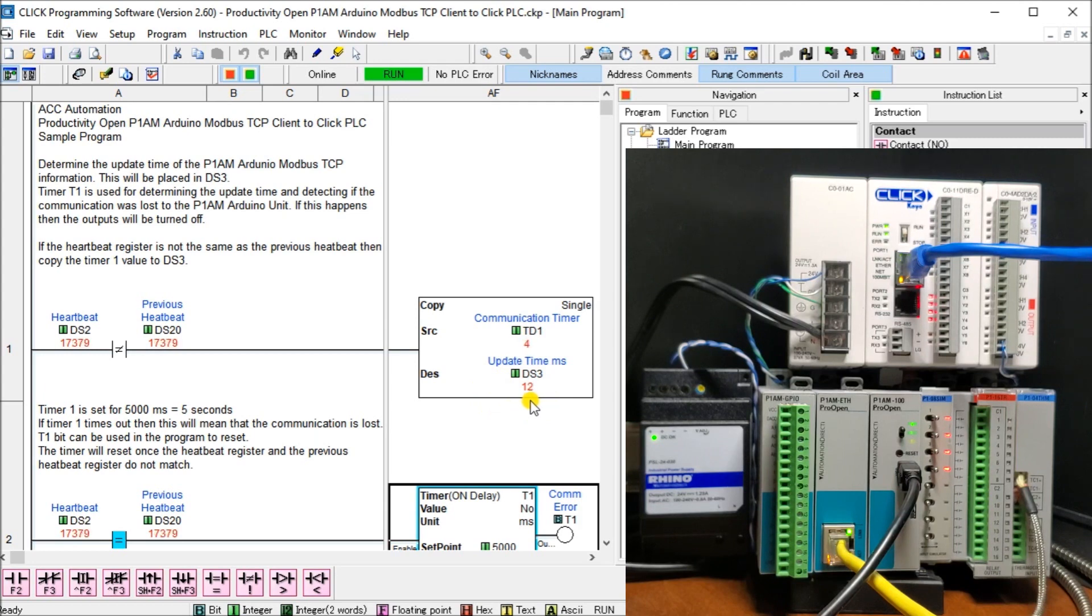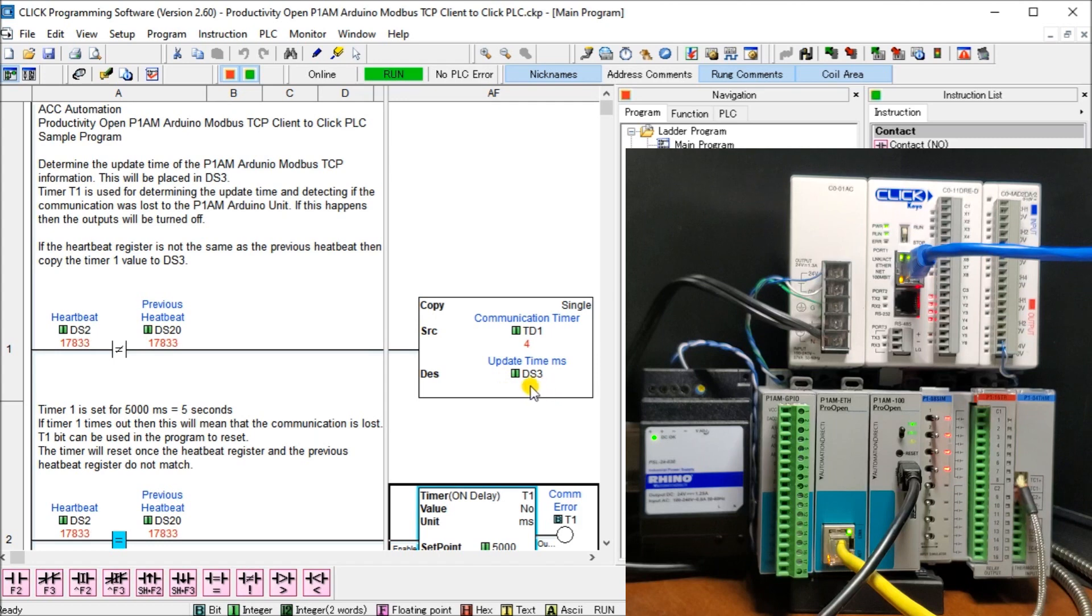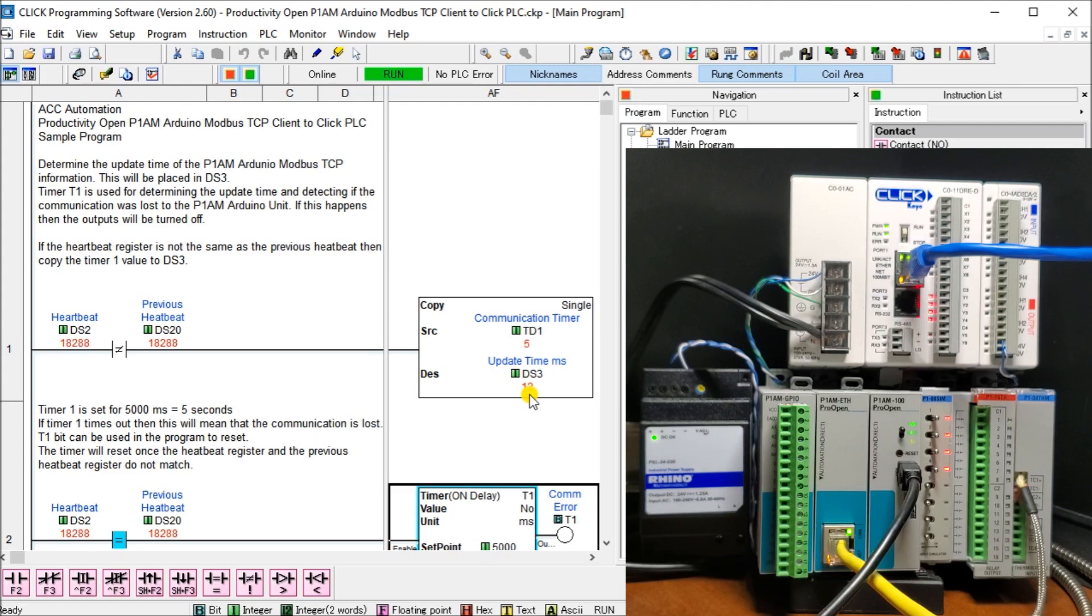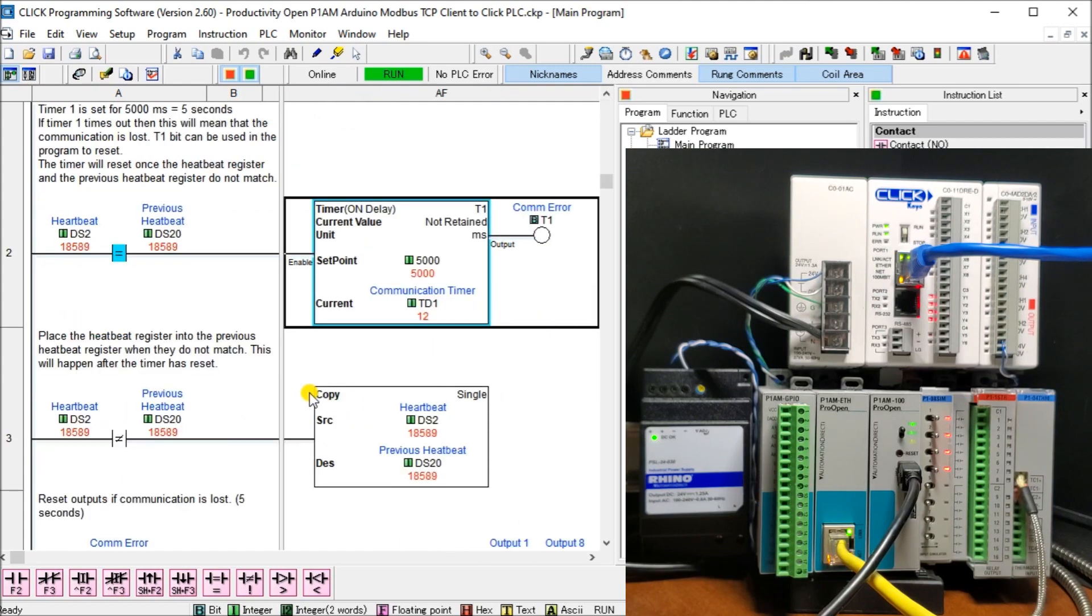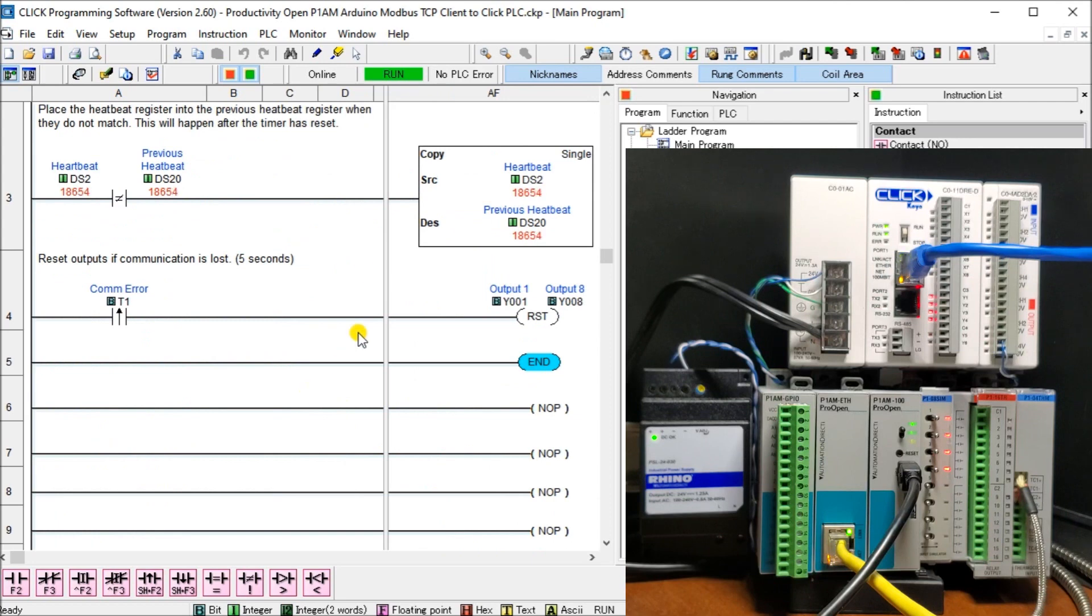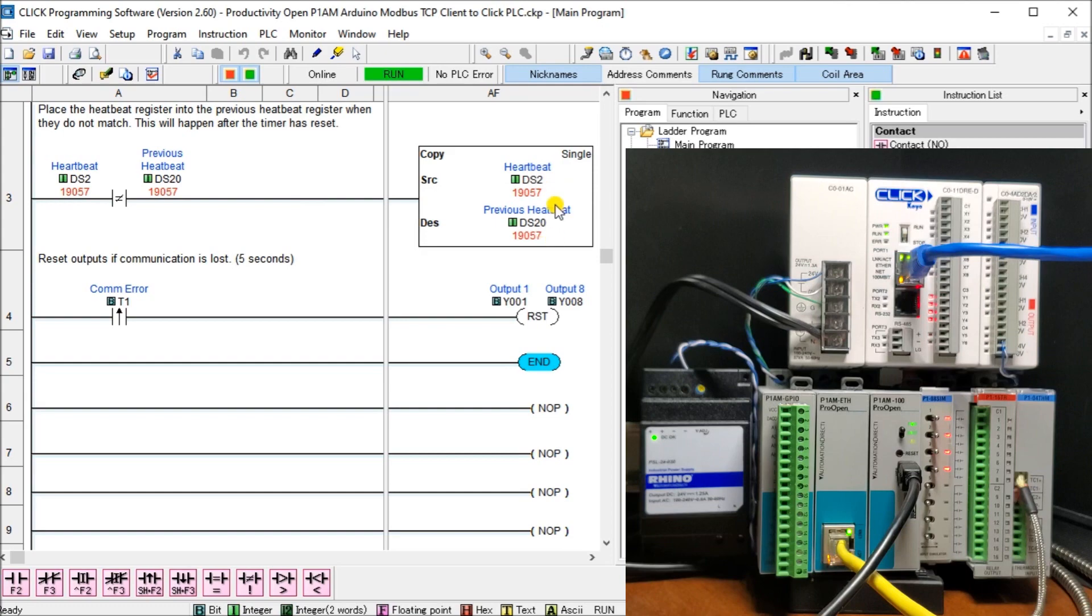And DS3 is telling me how many milliseconds it takes between those numbers that we're seeing incrementing on our unit. Which in this case here, we're anywhere from 12, 12 or 13 milliseconds is our update time or throughput for our Modbus TCP network.